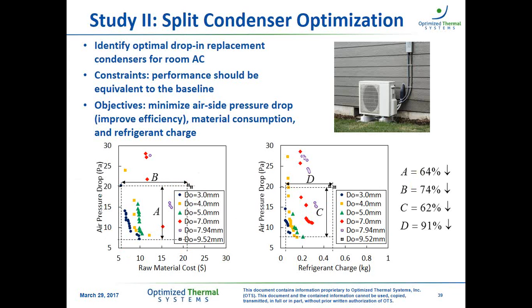B indicates the raw material cost. This is basically reducing 74% of the material between this heat exchanger and this heat exchanger. And again, all of these designs are delivering the same heat capacity. So it's pretty interesting to see how much less material is required to do the same job. And lastly, we have the refrigerant charge. Here we have a potential of up to 90% refrigerant charge reduction within the heat exchanger. Now again, we need to remember that this is a charge reduction inside the heat exchanger. It does not mean that you're reducing the overall charge of the system, because we're not changing other components, including connection pipes, the compressor, or in this case, even the evaporator. But a significant reduction in charge in the condenser will obviously lead to a reduction in charge in the system.